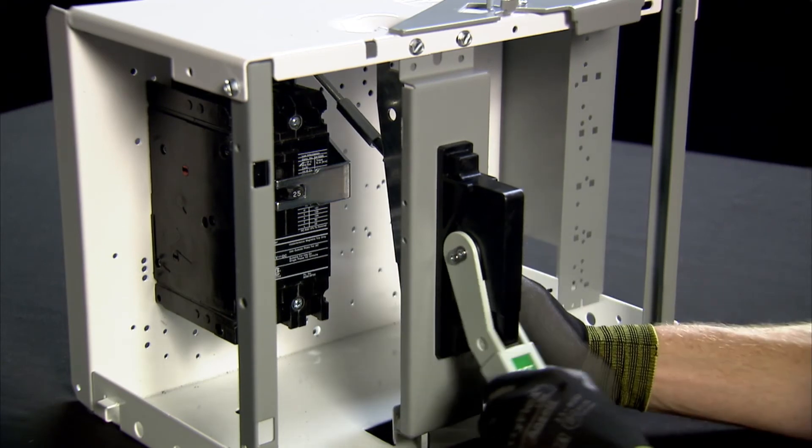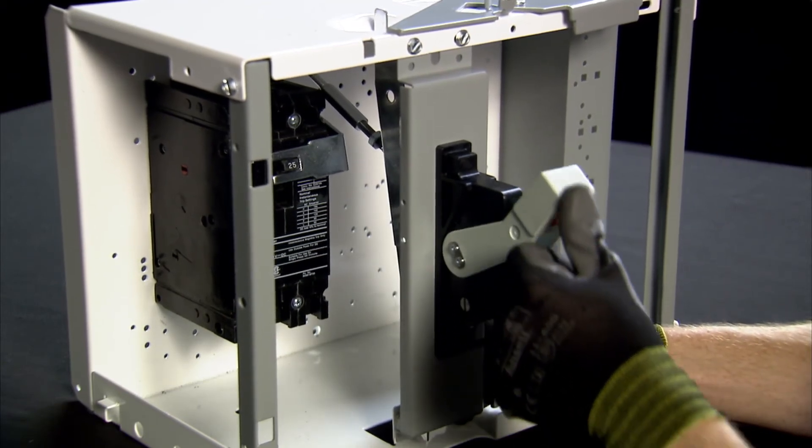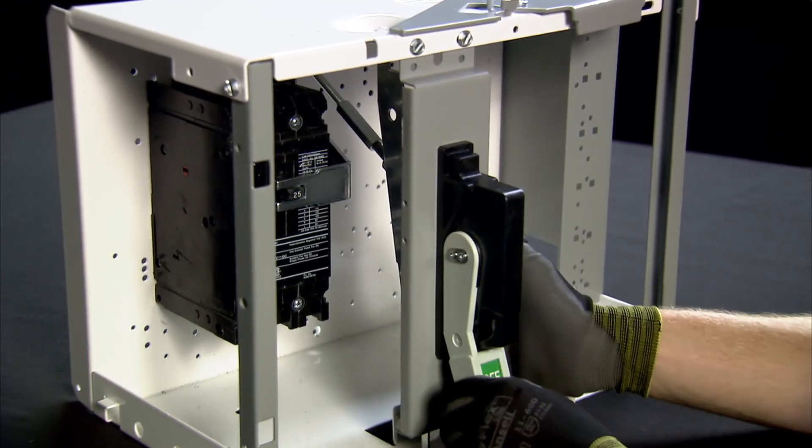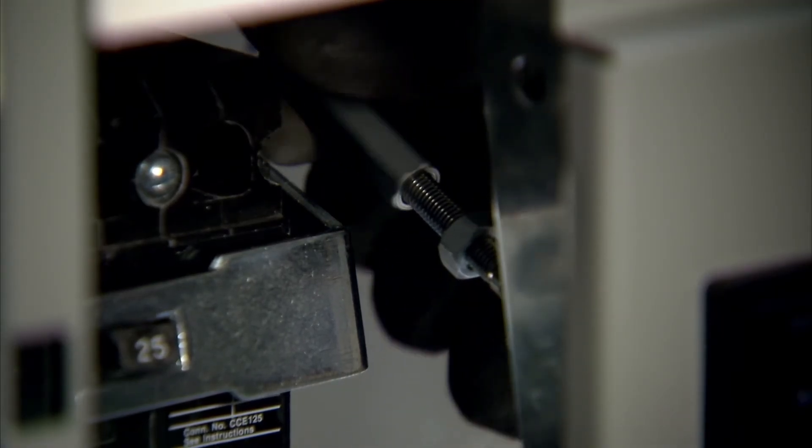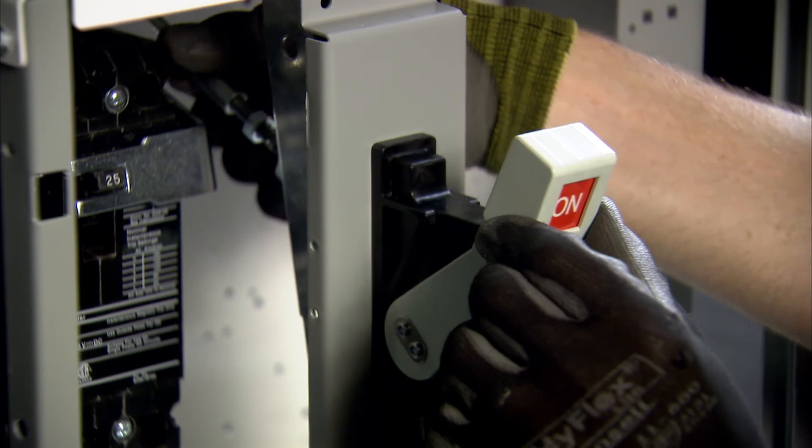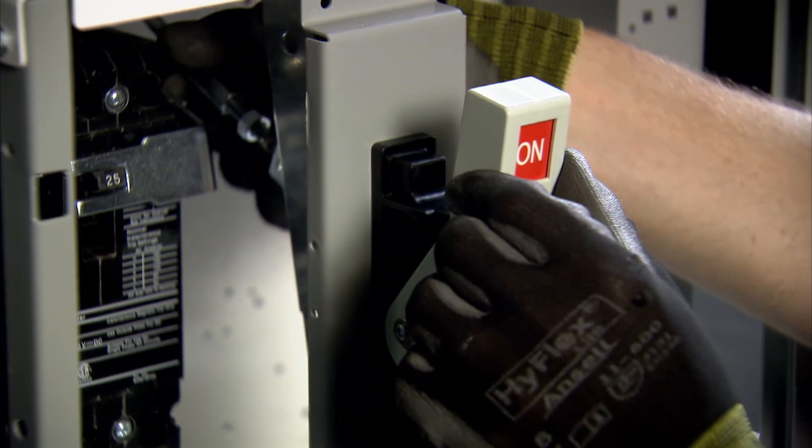If the handle will not move into the on position, the length of the linkage rod is too long and must be shortened. Rotate the turnbuckle counterclockwise to shorten the rod and move the handle up towards the on position.